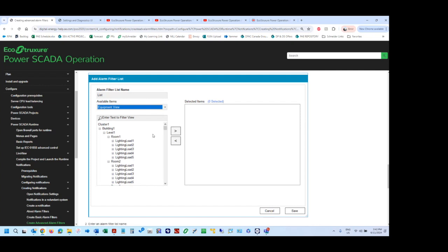Yeah. And that's done through, okay, that's a good example question. So, below a certain level for a certain amount of time. I'm going to suggest we can do it in two ways. One way, off the top of my brain, I know how to do. The other way, I don't. So I would lean towards the easy way, which is probably already the way that you know how to do as well. We could create this framework as a set point module in the meter, and then just pull it as an alarm into the system. I like that way as well, because then we're creating the alarm on the meter as well as in the system.